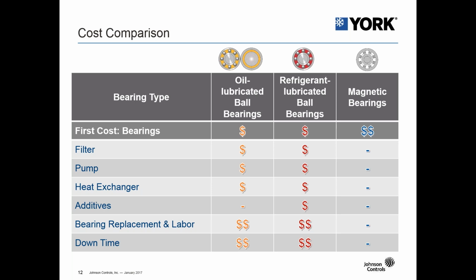From an oil lubricated ball bearing system to a refrigerant lubricated ball bearing system, there is a slight premium for the refrigerant lubricated, but nothing very significant. So we do have the added first cost of the mag bearings, but as you start looking at the total system and the maintenance and the potential downtime, that's where we see customers really understanding the value of magnetic bearings. So there's no filter replacements, there's no filter checks, there isn't a pump, there's no heat exchangers, there's no additives, and there's no scheduled bearing replacement that would result in downtime to do an inspection, and then also any labor required to take apart the chiller and make that change.